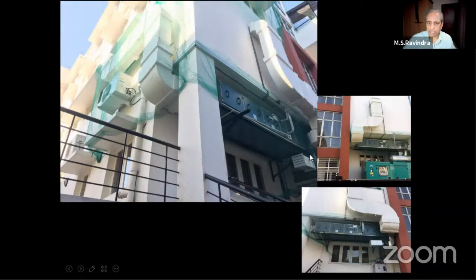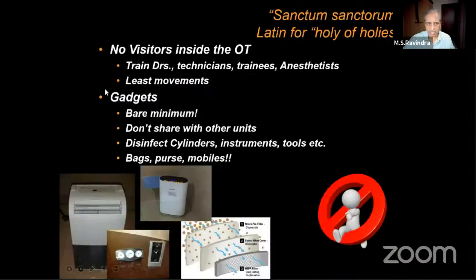In many other operation theaters, this care is not taken, and whatever air comes into the HEPA filter will be highly contaminated. That's one of the causes for coating of the ducts inside with dust. So you can see the AHUs, and you spare the floor area - floor area is totally spared by considering that.